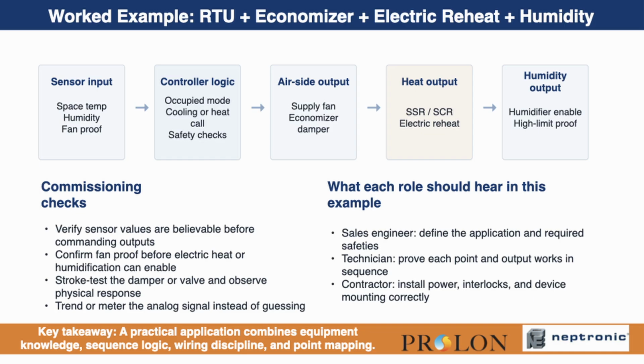Just to clarify, SSR, solid-state relay. An SSR is an electronic relay with no mechanical contacts. It uses semiconductor components to switch a load on/off based on a control signal. Typical use: 1. Turning electric heaters on/off. 2. Switching humidifiers, small motors, contactors, or resistive loads. 3. Replacing mechanical relays/contactors where silent operation and longer life are desired. Typical control signal: 24 volts AC, 24 volts DC, 0 to 10 volts DC, depending on model. Key point: SSR is mainly an electronic on-off switch. Example: a controller sends a signal to the SSR, and the SSR energizes an electric duct heater stage.